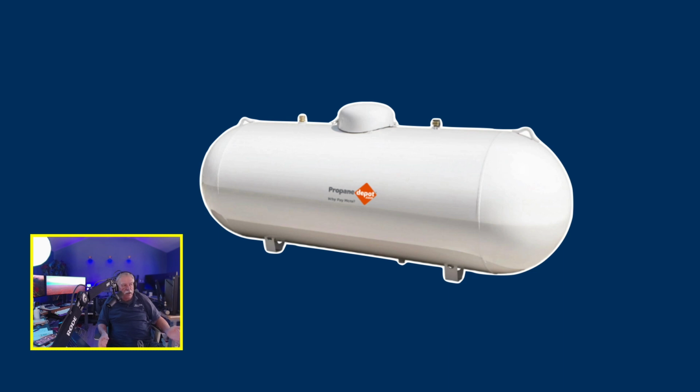Now, the big thing is you have to have fuel installed on your property. In this case, as an example, is a 1,000-gallon propane tank. Typically, code requirements has it where we bury that. That's expensive. And propane averages, it goes up in the summer, down in the winter, supply and demand, about $3 a gallon. And a generator will burn about 3 to 4 gallons an hour. So you can run out of propane and you have no power.